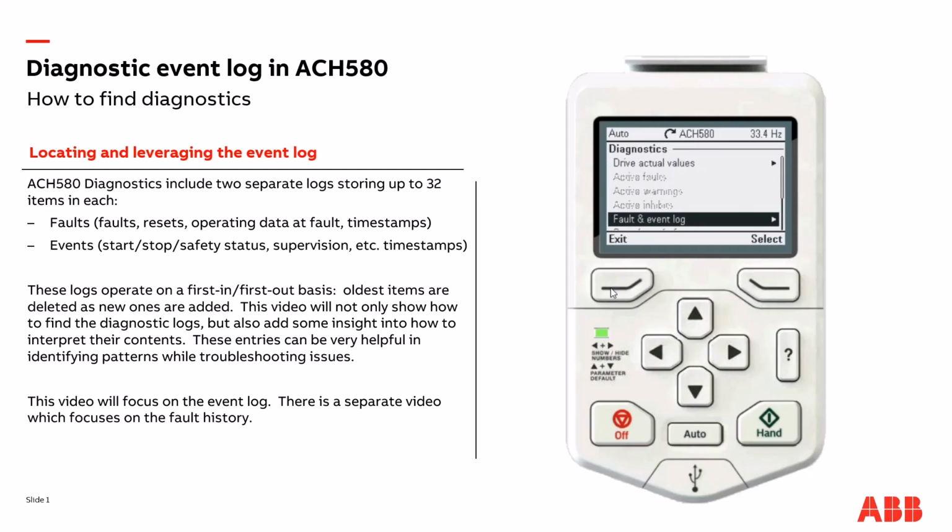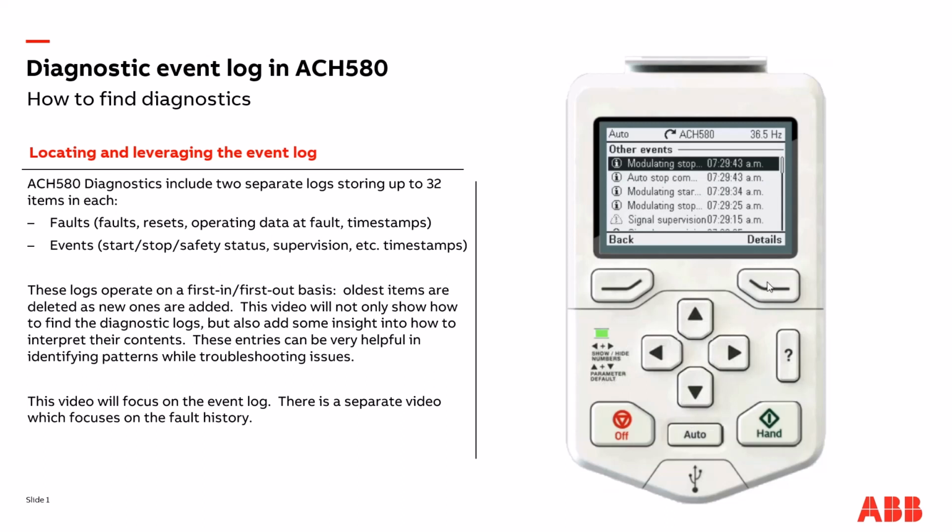Here we can now see that we're starting from a completely cleared state again, just like we started. One additional item here that I neglected to cover, and that is what is actually in the event log on a particular entry. So let's go back into the event log and select one of the events and navigate just a bit deeper and see, well, what is the content here? Okay, so here's the details. We get, of course, the textual description of it. As well, we get the corresponding hex code. And then we have what's called the aux code.